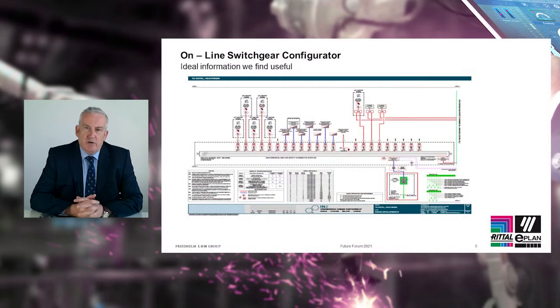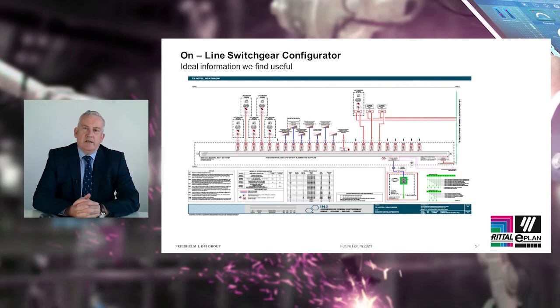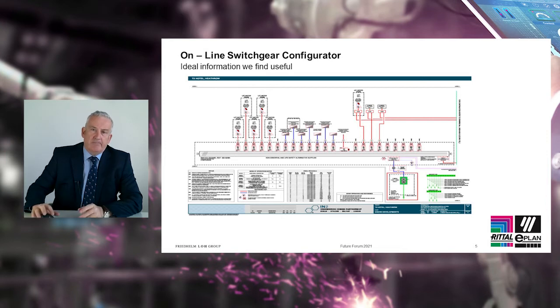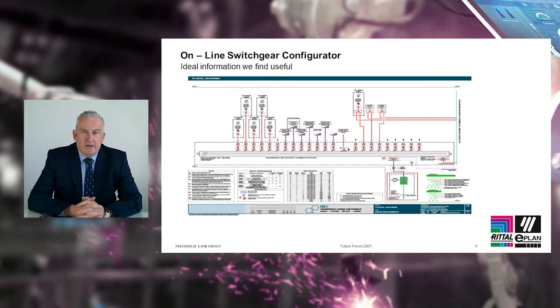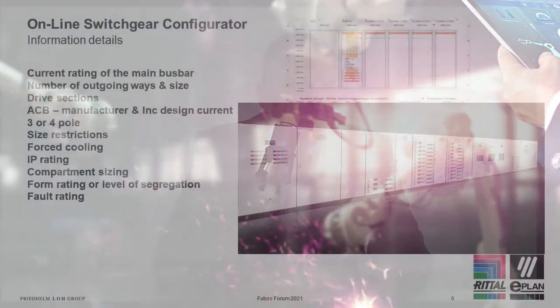Before you can use the configurator, it needs some basic information for the switchgear design. Engineers know from the specification that they need to be clear what they're designing. So there is basic information that we need to configure the software. The key one is the schematic drawing, as you can see there. If you do have a schematic drawing, that is great. If not, there's some basic information that we do need to configure the system.